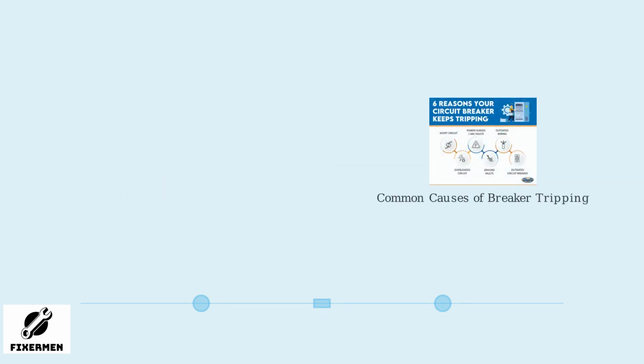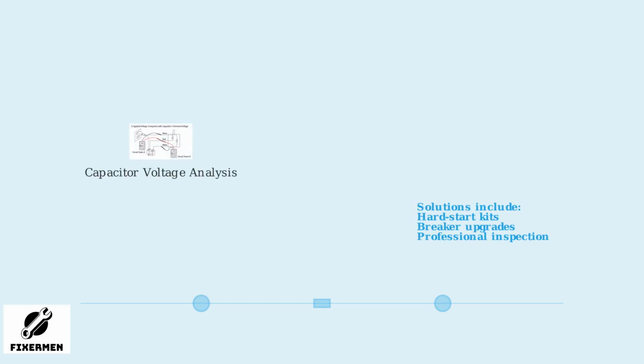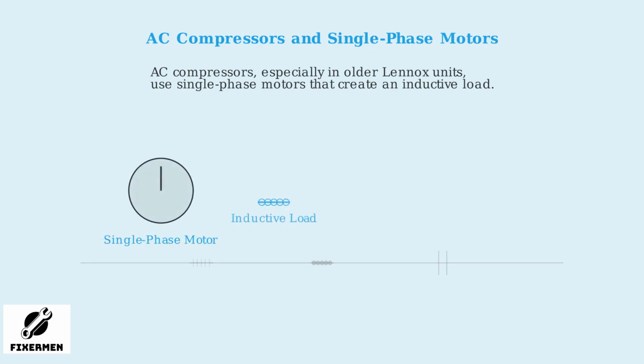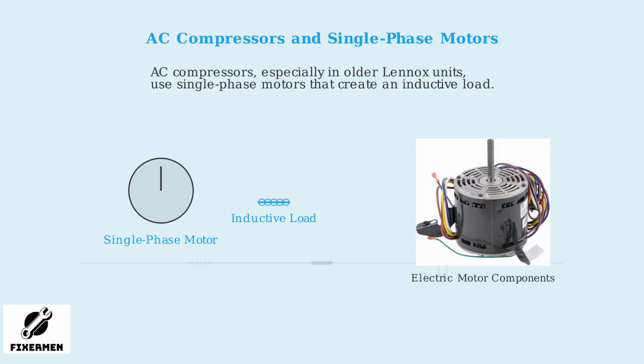Several factors can contribute to this problem, including electrical faults, wiring issues, and power surges. Understanding these causes helps identify solutions. The issue often relates to capacitors and electrical components. Solutions range from simple upgrades like hard start kits to professional electrical inspections. AC compressors, especially in older Lennox units, use single-phase motors that create an inductive load, demanding a lot of power initially. This motor design is typical of those found in Lennox AC compressors.